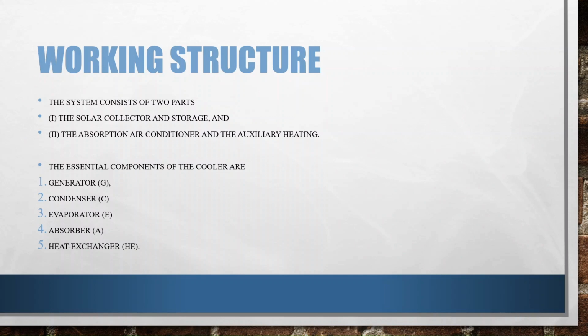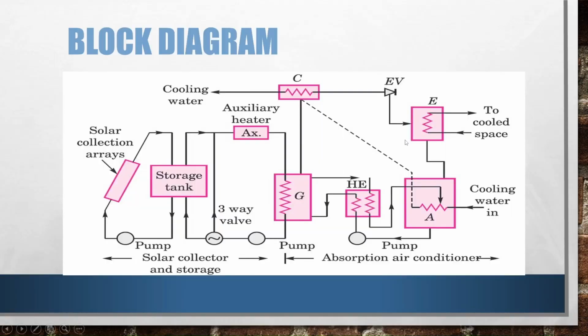Coming to the working structure, the system consists of two parts: the first is the solar collectors and storage, and the second is the absorption air conditioner and the auxiliary heating. The essential components of the cooler are the generator, condenser, evaporator, absorber, and heat exchanger. Coming to the block diagram, as we can see, we have solar collection arrays, a storage tank, a pump, a three-way valve, an auxiliary heater, the cooling water inlet, and another pump to send it to the heat exchanger, and an exchanger to the cool space.